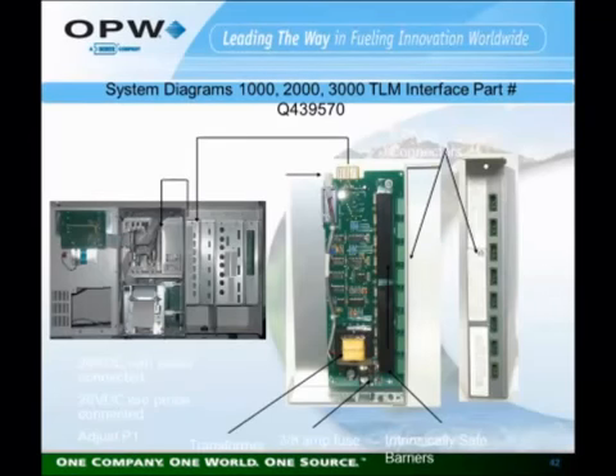The TLM Interface Module is normally installed in the right-hand portion of the unit. Left-hand portion containing the backplane board, the card cage, power supply, printer, and customer interface. The right-hand side, the interface modules for the external devices. The TLM Interface module is normally the first module. It has 8 connectors on it to connect the field wiring for 8 tank probes.